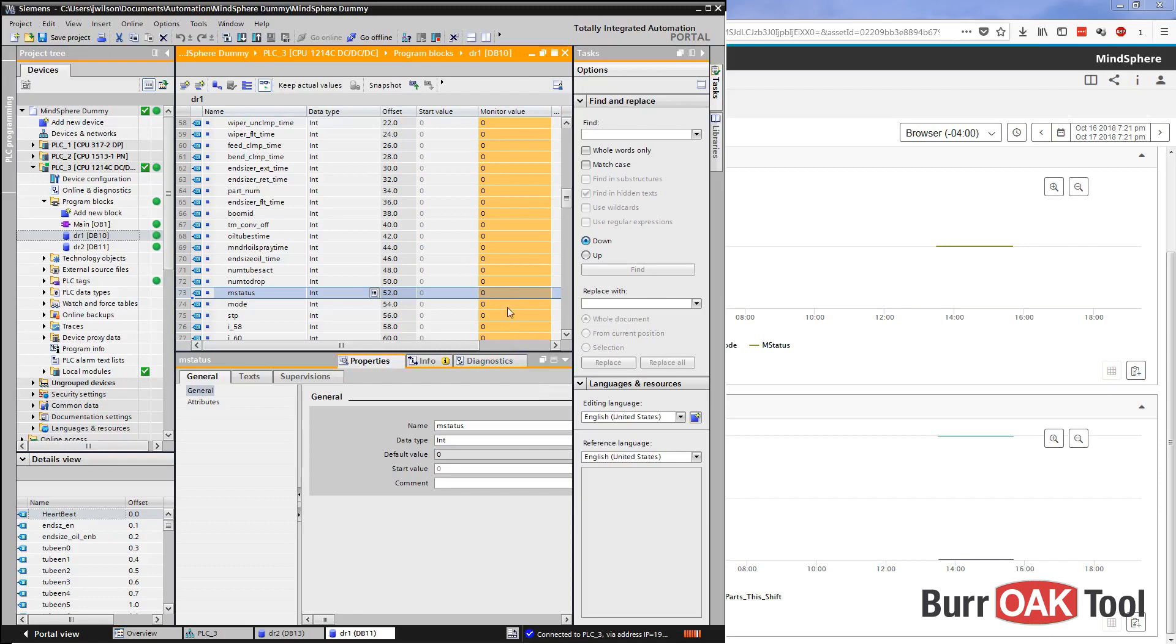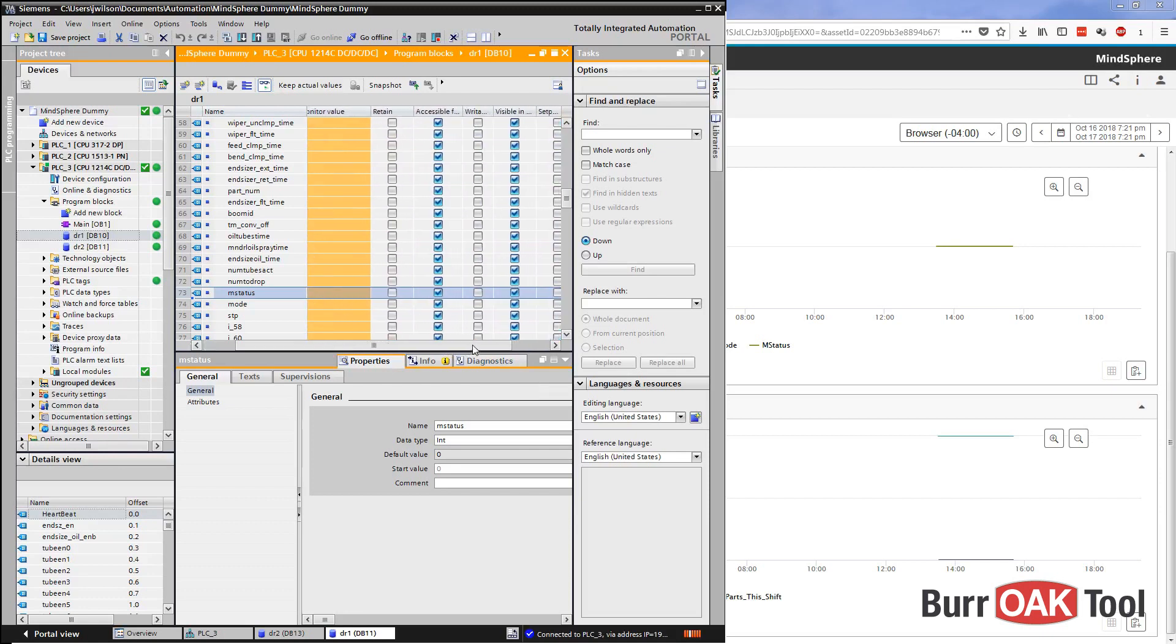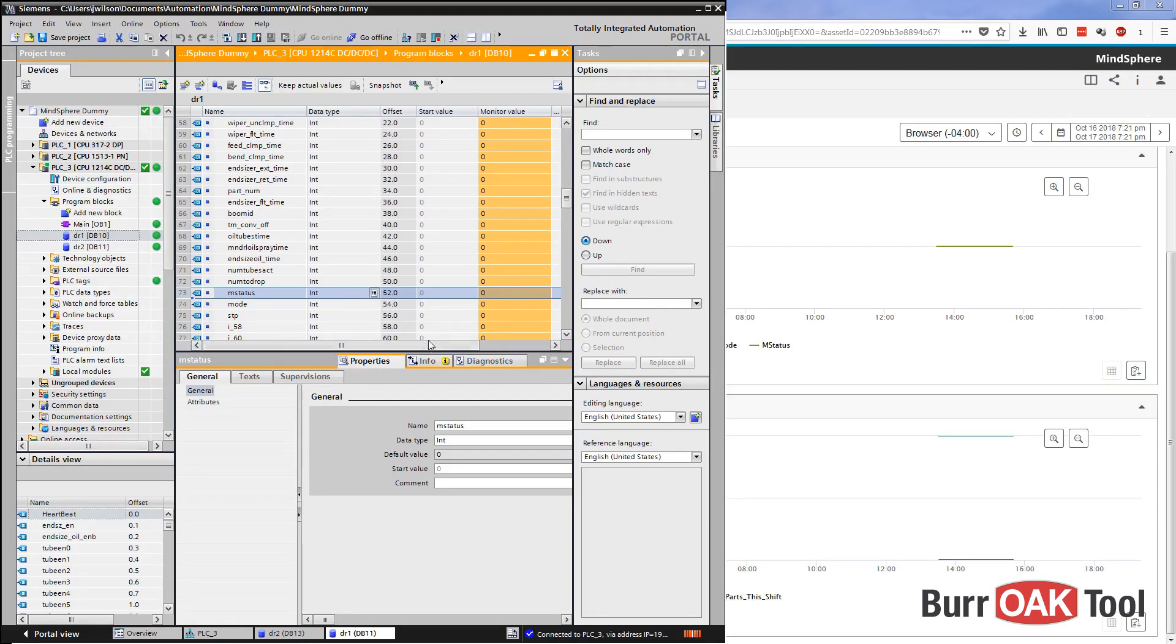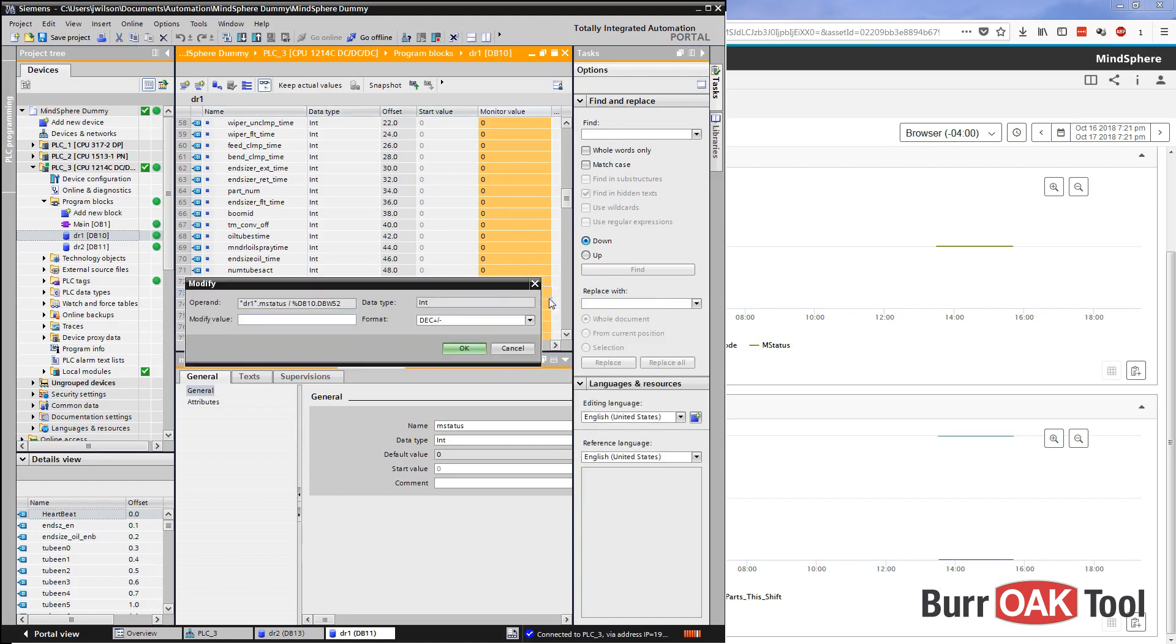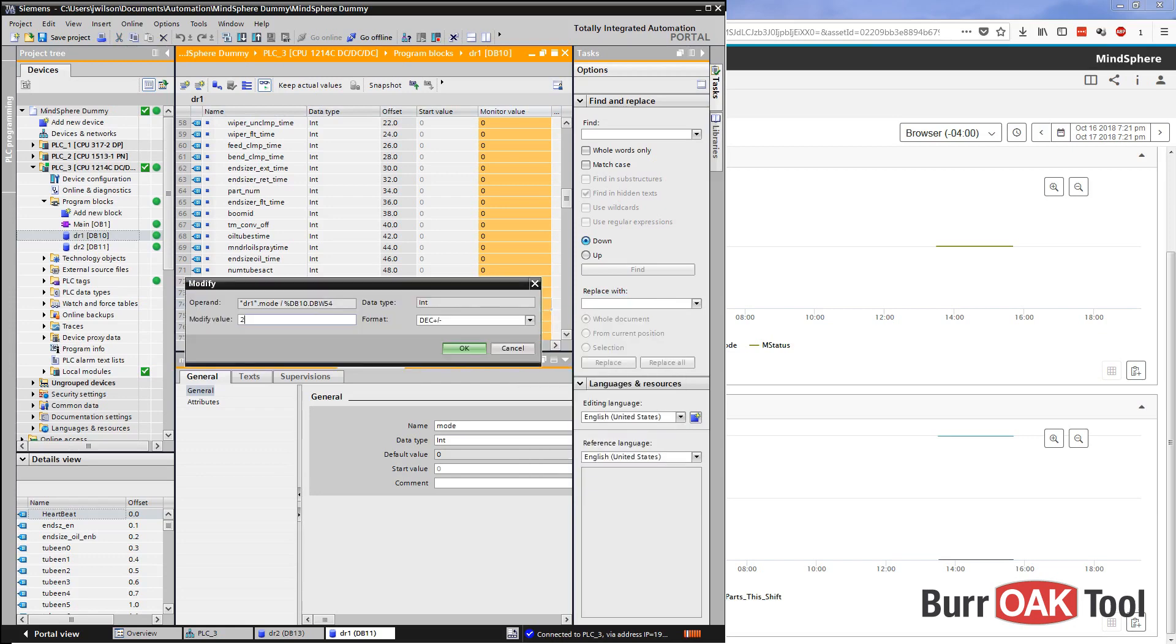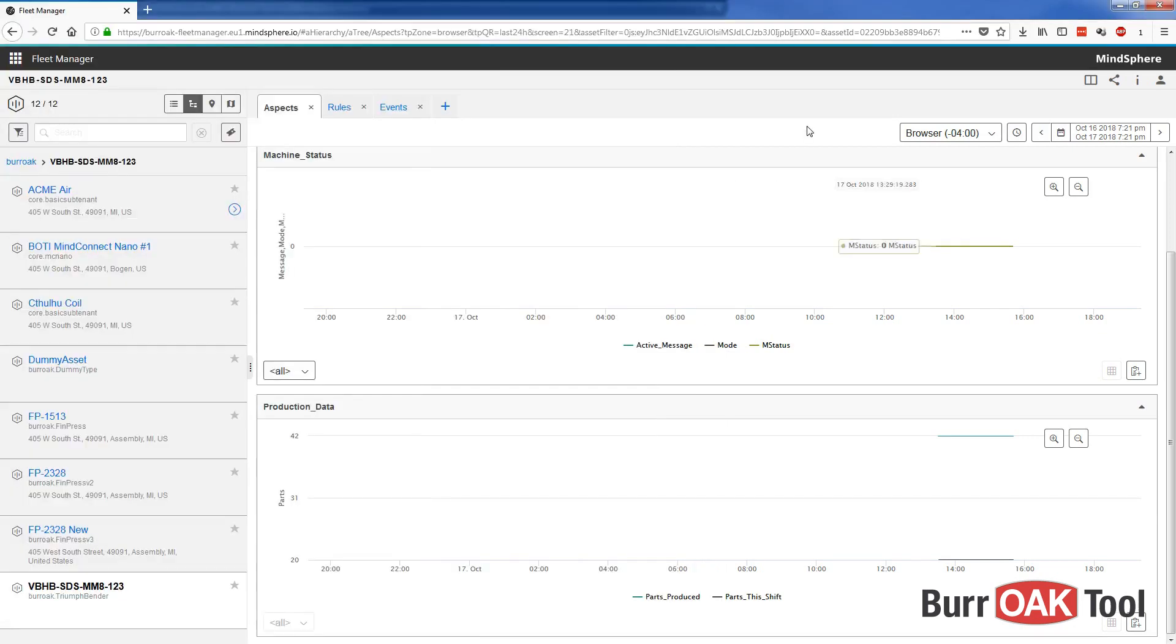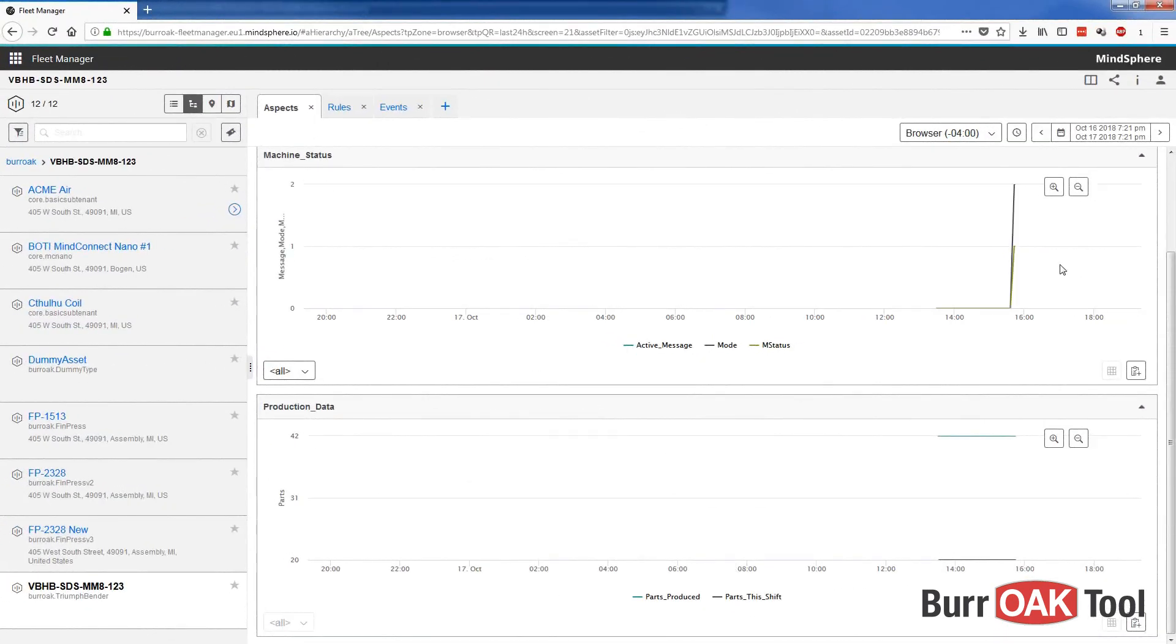Looking at TIA Portal, we can see that these are in fact set to zero. I had forgotten to set the retain bit for my test PLC, and then I had cycle power. So I'll try changing these. Modify this to one, and this to two. And then we'll watch over here. And then these should change in just a minute here. And there it is. See that those two values just changed? So we know that we did, in fact, map our data values correctly.